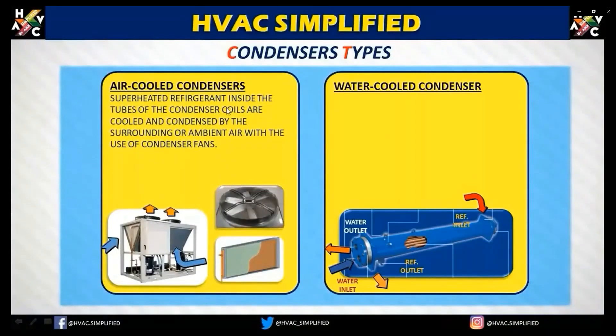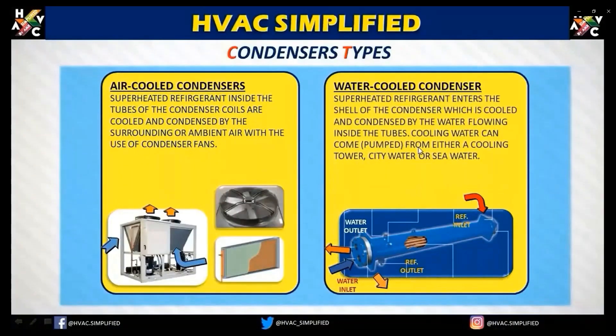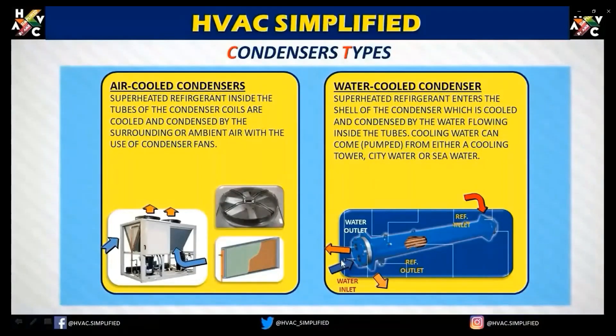Superheated refrigerant inside the tube of the condenser coil is cooled and condensed by the surrounding ambient air using condenser fans. In a water-cooled condenser, superheated refrigerant enters the shell and is cooled and condensed by water flowing inside the tubes. Cooling water can be pumped from either a cooling tower, city water, or seawater — it is a shell and tube type where water acts as the medium.